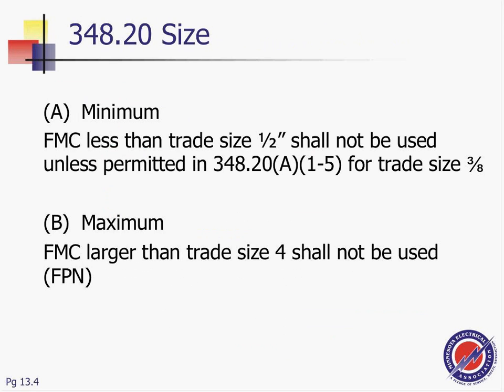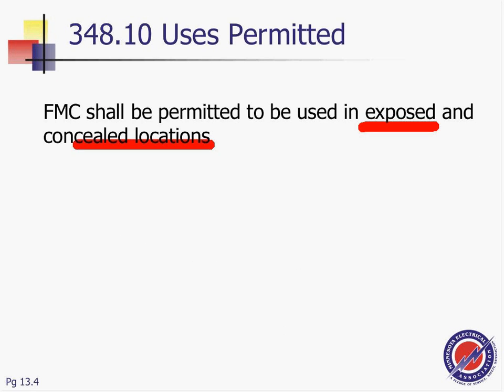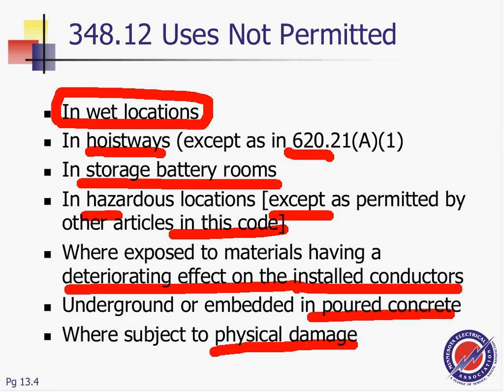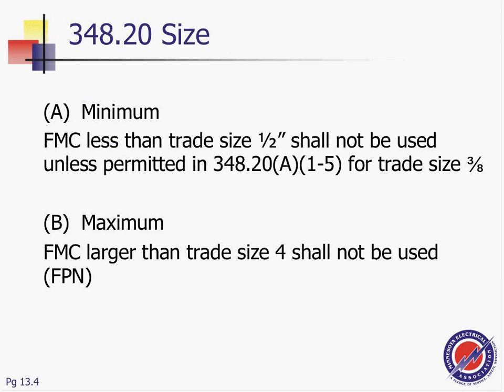The important thing about uses, I can't emphasize enough: I can use it exposed, concealed, with limitations in certain areas, especially the wet location. You can get it from 1/2 inch all the way to 4 inches. There is also 3/8, and they use it a lot with fixture whips. They call them fixture whips. And there's a table, guys, that you can use for sizing the conductors you can fit in 3/4 inch flexible metallic conduit. We will get to it in a second here.